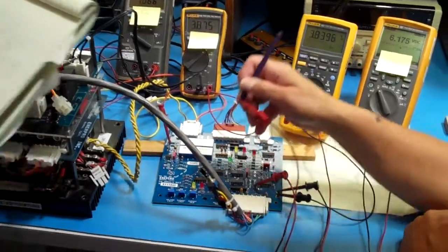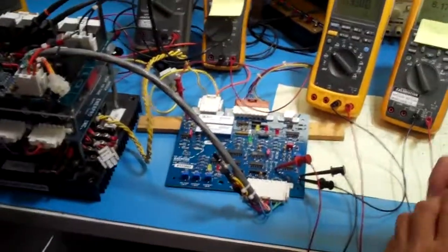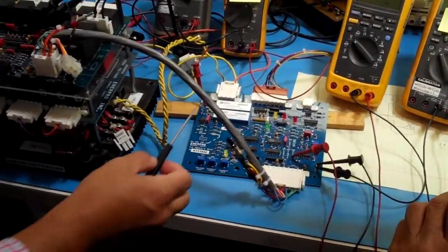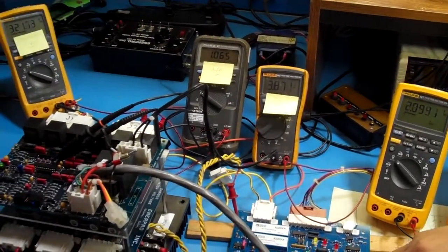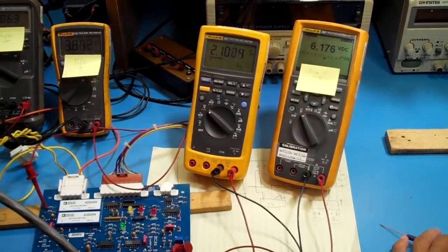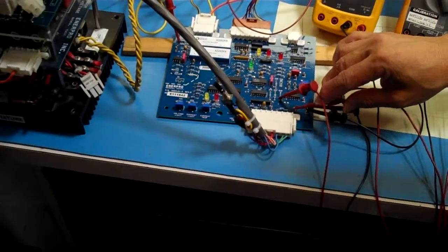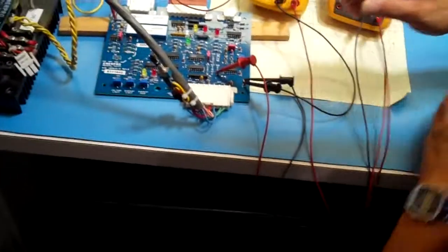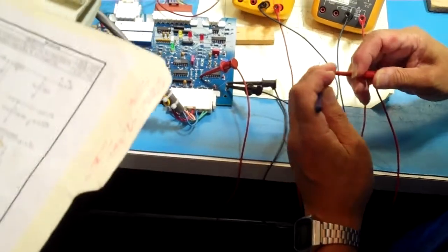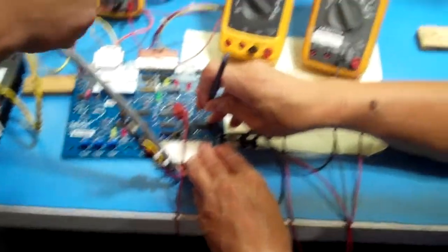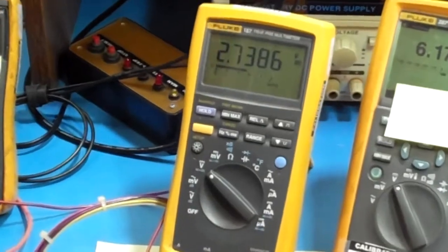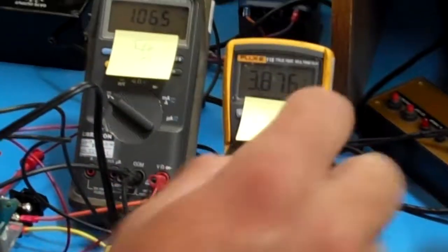Now let's do the same thing with the current. First of all, remember, we got TP1, so we go to TP1 and we should have twice that 1.065, which is roughly 2 volts, and we do. Okay, now let's go to that part of the circuit that compares those 2 volts on TP1 against the current trip. So we're going to go to U10 position 3. And the same idea, the 2.73 is greater than the 2 volts that we get on TP1.